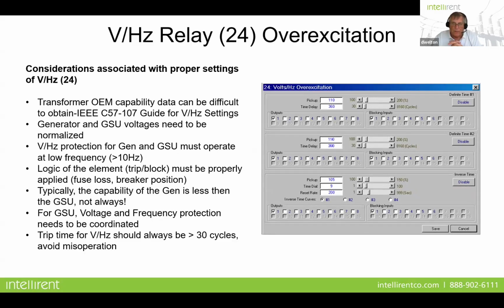Now, one thing I want to talk about is volts per hertz or overexcitation protection, and I think this is one that gets misunderstood very easily. Okay, volts per hertz is a relationship of voltage to frequency. It's not a voltage element, it's not a frequency element, it's a combination of both. So generally where we see this enabled is on a generator, but not always. It could be on an EHV or a high voltage substation. You could have volts per hertz enabled there as well, and I'll get into that in just a second. But basically, it's looking at the percentage difference between the voltage and the frequency. So in this setting right here, what we have is a pickup of 110%. So if our voltage and frequency have a difference of 10%, after 360 cycles, it's going to trip.